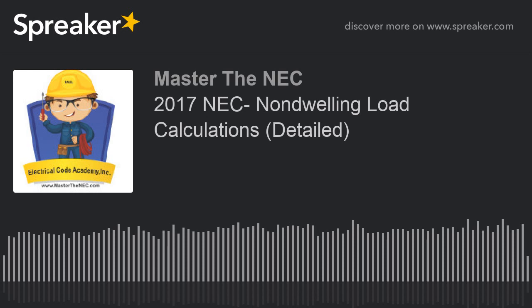Okay, so let's kind of look at it. So let's say we had a commercial electric cooking equipment. It'll have a nameplate value. We have the dishwasher booster heater. We have a water heater. And we have other kitchen equipment. And we're going to use table 220.56.